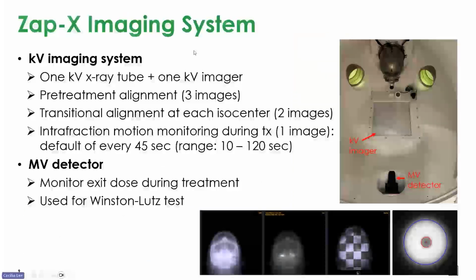So the machine has a kV imaging system. It has only one kV X-ray tube and one kV imager. So 3 images are taken for pre-treatment alignment at predetermined gantry angles, and for each isocenter 2 images are taken using the beam angle. And then during treatment only 1 image is taken every certain number of seconds, but the default is 45 seconds. You can choose anywhere between 10 and 120 seconds.